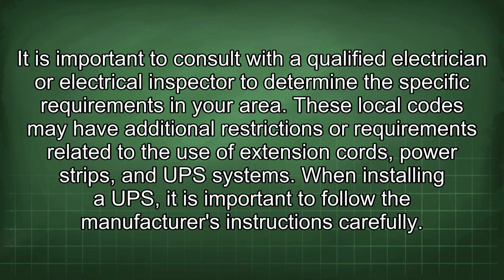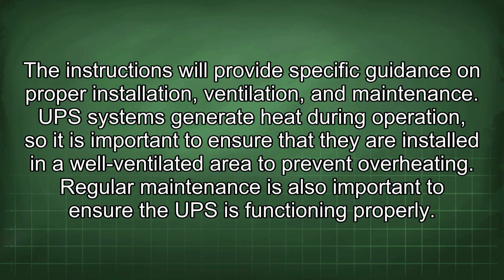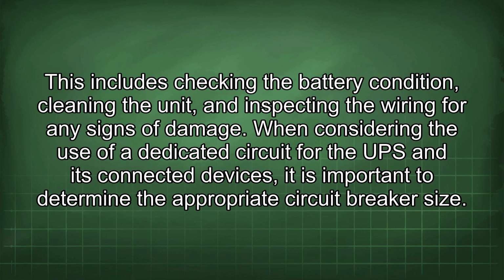When installing a UPS, it is important to follow the manufacturer's instructions carefully. The instructions will provide specific guidance on proper installation, ventilation, and maintenance. UPS systems generate heat during operation, so it is important to ensure that they are installed in a well-ventilated area to prevent overheating. Regular maintenance is also important to ensure the UPS is functioning properly. This includes checking the battery condition, cleaning the unit, and inspecting the wiring for any signs of damage.